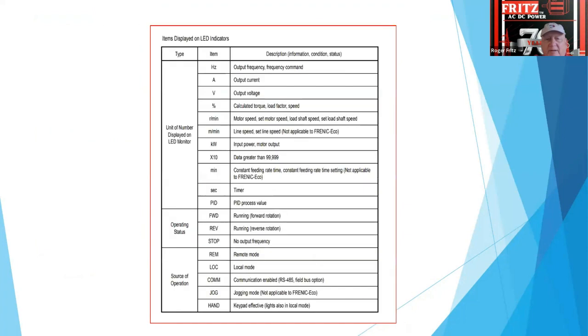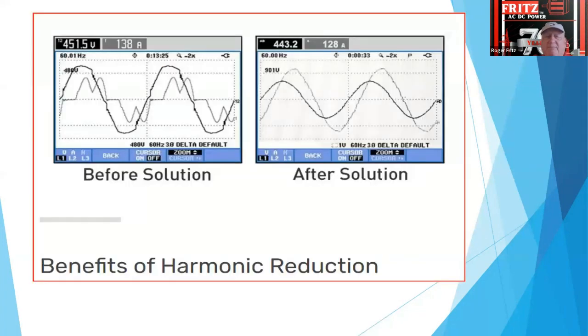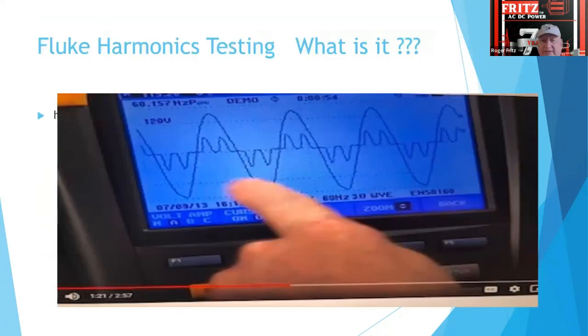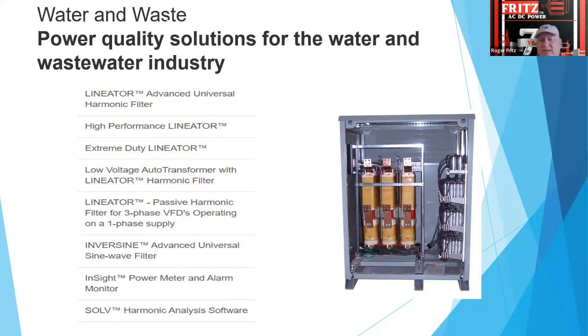I guess I don't have the calculation on this particular slide, but the resultant was, just by cleaning up the harmonic content into the building, it ended up saving right at about 15% of the front end power just from harmonics. Then when we cleaned the power factor up, we ended up eliminating all those power factor penalties in addition. So we like to see a building cleared up. We have a filtering network. Besides this, what they call a static filter, we also have an active front end one.